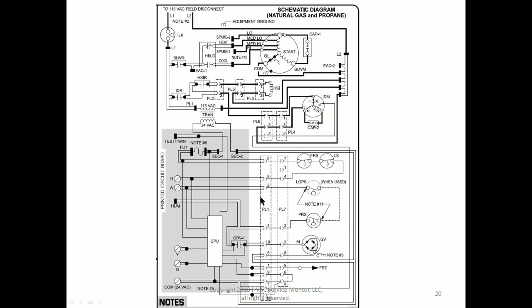So first of all, what are the loads that this control board controls? Beginning with our high voltage loads, we've got this one. This is our blower motor. We've got this one here. This is our hot surface igniter. And we've got this one here, which is our induced draft motor. There they are. It controls three things. That simplifies things, doesn't it? And on the low voltage side, what are our low voltage loads? There's only one. There's a gas valve. Okay, so that's what it controls.